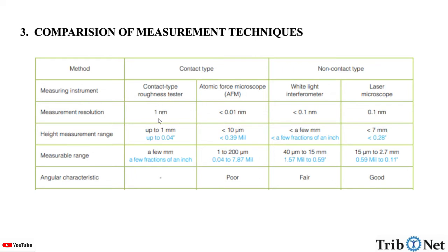Height measurement range for contact type roughness tester is up to 1 mm, and for atomic force microscopy it is less than 10 µm. For optical profilometer it is a few millimeters, and for laser microscope it is less than 7 mm.